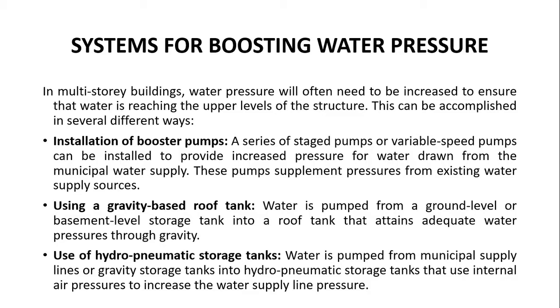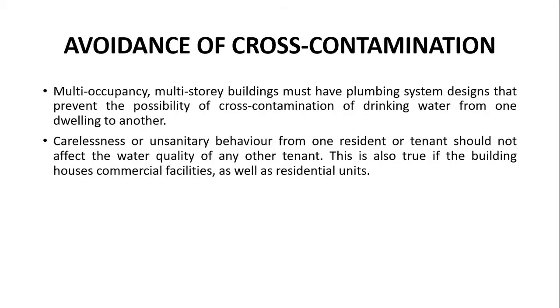The second system is a gravity-based roof tank. Water is pumped from the ground level or basement level storage tank straight into the roof tank, and then that water acquires sufficient pressure due to gravity as it reaches the lower stories. Of course, to pump water from ground level to the roof level, we still need a booster pump. Third, we use hydro-pneumatic storage tanks. Water from the municipal supply lines or gravity storage tanks is pumped into the hydro-pneumatic storage tank, which uses internal air pressure to increase the water supply line pressure, and then water is pumped at adequate pressure to the various stories in the building.